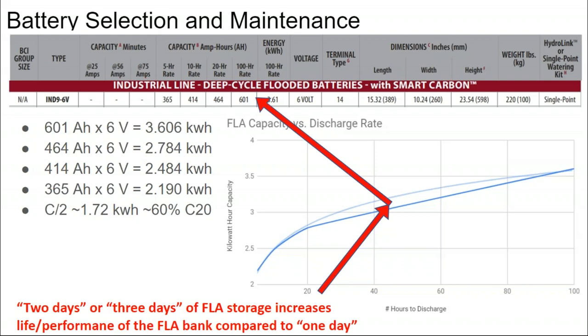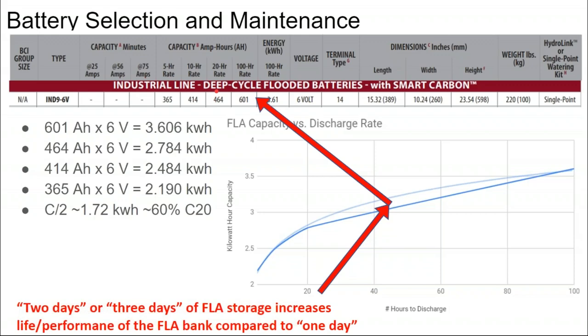But if we're talking about 2 or 3 days worth of power, at that point lead acid starts to make its way back up into cost effectiveness, because the battery bank is literally a larger battery bank at a slower discharge rate versus a rapid discharge rate.